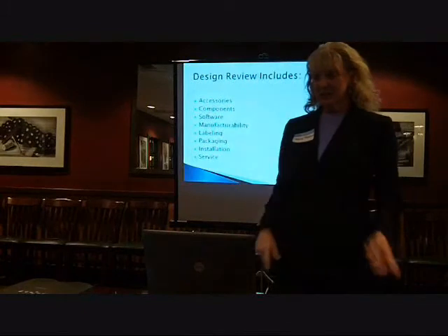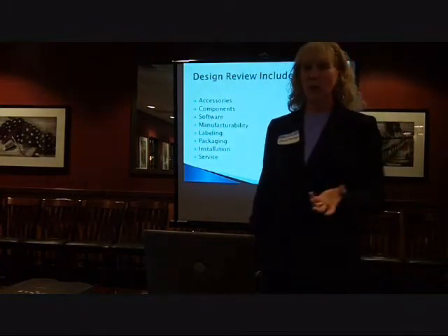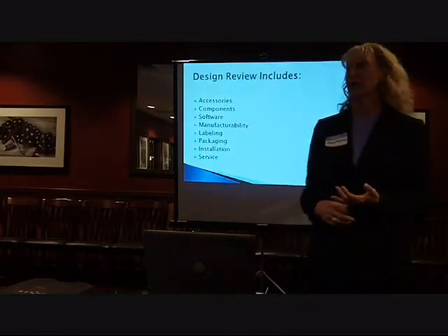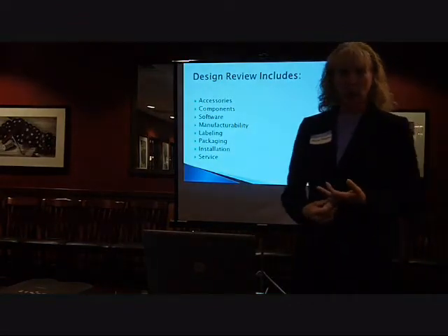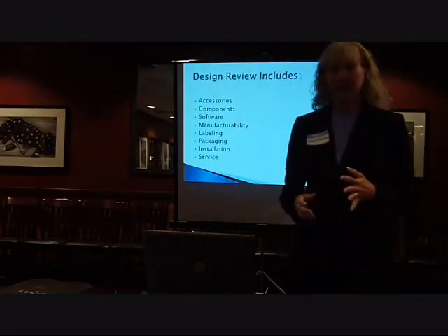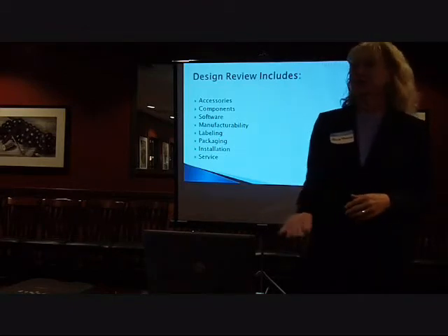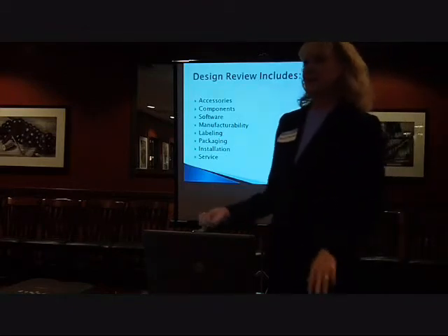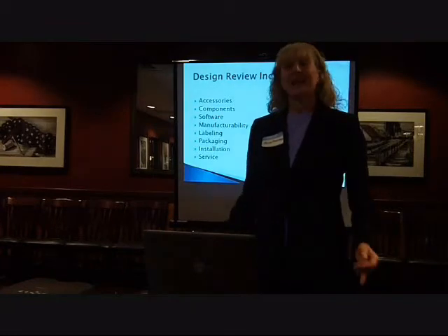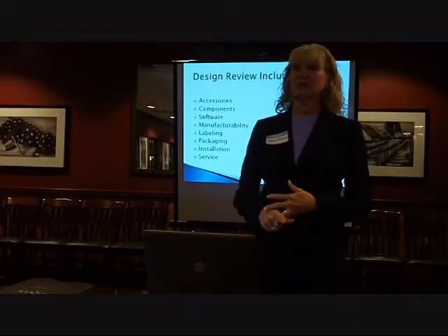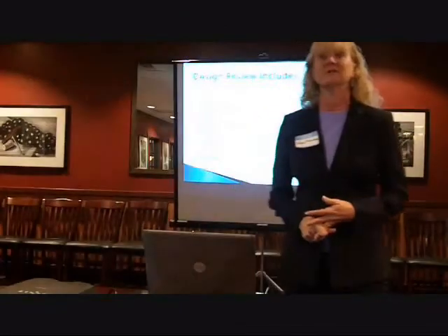Design review looks at everything. So if you have accessories to the device, it looks at the components. What are you making this of? Are you going to be able to really get those components? What are some of your requirements on those components? It looks at the software. Is it manufacturable? Can we actually make this device? It looks at labeling. Packaging, especially if you're making sterile devices, becomes even more important.